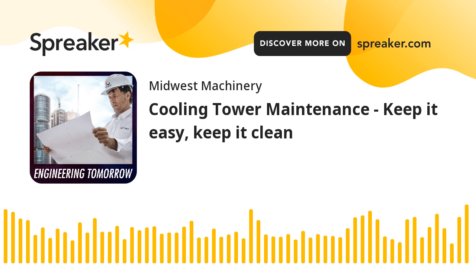And I guess, is it still accurate to say using a cooling tower is one of the most efficient methods of keeping your building cold? Well, working with water is definitely one of the more efficient ways to go. A lot of people like air handling units or rooftop units, which are just a single unit ducting air into a room. But using water, incorporating a cooling tower, is definitely more efficient, lasts a lot longer, and requires less maintenance than any other sort of air device.